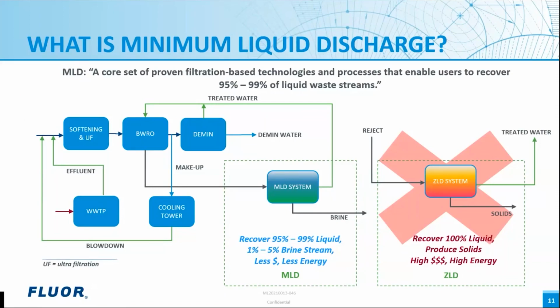Let us first define ZLD, which is a water treatment process in which all of a facility's liquid waste is purified, recycled, and therefore leaves zero discharge at the end of the treatment cycle. At the same time, it produces solids from the liquid stream, which may be recovered in some cases or disposed. A typical ZLD system can include process technologies such as ultrafiltration, reverse osmosis, and most typically evaporators and crystallizers.